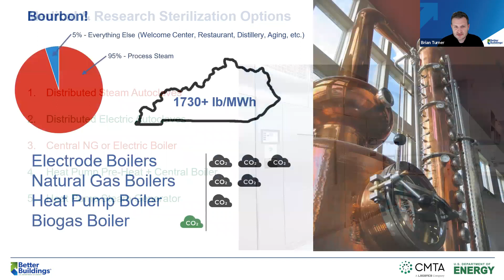We have a project where the steam generators for the boilers for the bourbon stills account for the vast majority of energy usage on site. Options include electrifying with an electrode boiler, but at that emissions intensity, that's the dirtiest thing you could do unless you pair it with tens of megawatts of solar, which can be done. Another option is the traditional natural gas boiler method, but that's also very carbon intense, especially considering fugitive methane.